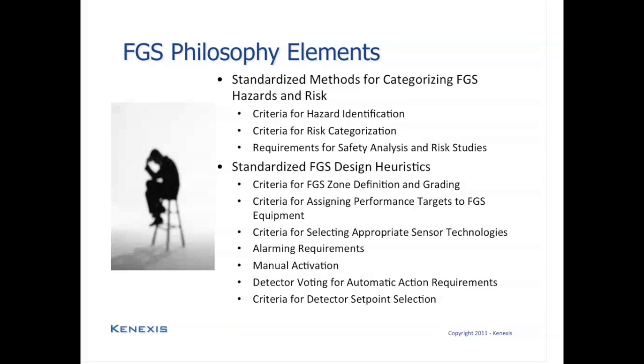There will be criteria for assigning performance targets to various fire and gas system equipment. There is going to be criteria for selecting which type of technology is going to be appropriate for the various types of sensors that are available for detecting fires and detecting gas releases. So, for instance, rules of thumb for when to use frangible bulbs or bimetallic heat detectors as opposed to optical fire detection equipment. There will be rules of thumb for how things are alarmed, when they are alarmed, and what those alarms look like in terms of audible annunciation and visible signaling. There will be rules of thumb for when manual activation is required and where those manual activation systems or manual alarm call points, MACs, will be installed.